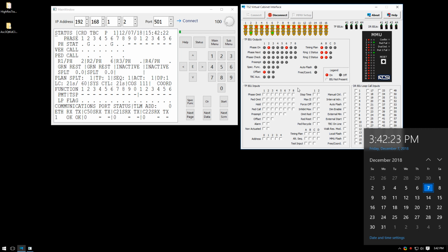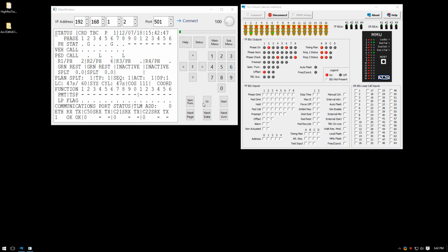The next step, I'm going to put a call on our side street, or our non-coordinated phases, which are phase 4 and phase 8, at around 3:42:30. And then I'm going to take the calls out at 40. Then I'm going to wait a little bit to get that call served. What will happen is the main line is going to go to the side street and the peds are going to get served.